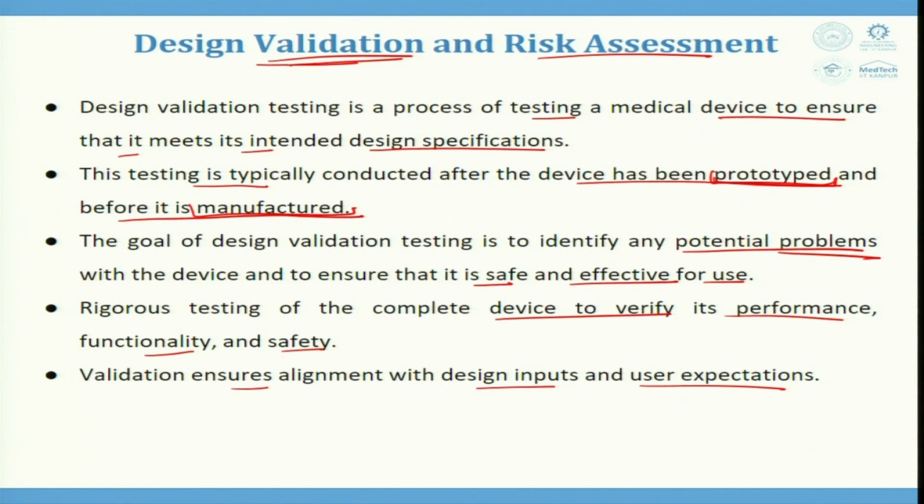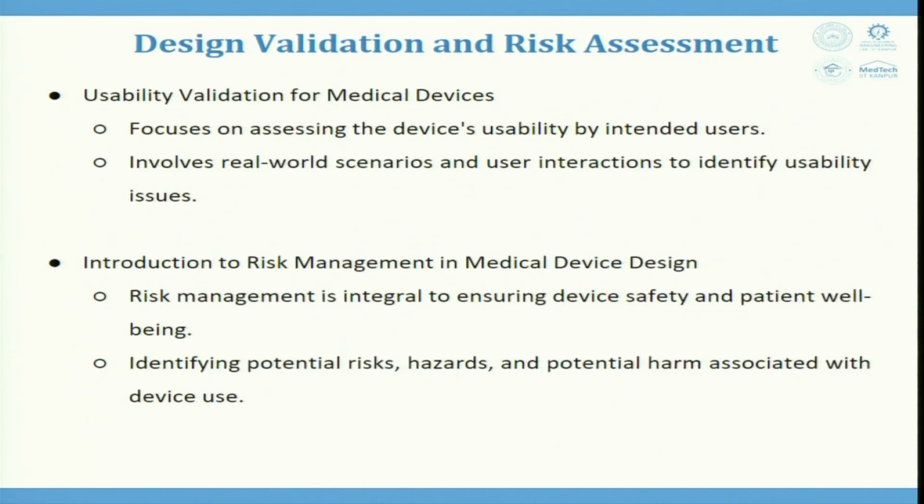Now, in design validation and risk assessment, there are certain points which are taken care of. For example, usability validation for medical devices. This focuses on assessing the device's usability by intended users, and it involves real world scenarios and user interactions to identify usability issues. Now, iterative testing to refine user interfaces or ergonomics or overall user experience is always applied. I would just write it here, iterative testing.